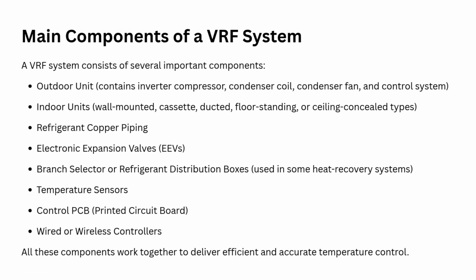Main components of a VRF system. A VRF system consists of several important components. The outdoor unit contains an inverter compressor, condenser coil, condenser fan, and control system. Indoor units include wall-mounted, cassette, ducted, floor-standing, or ceiling-concealed types. Refrigerant copper piping is used for refrigerant distribution. Electronic expansion valves, EEVs, control the refrigerant flow. Branch selector or refrigerant distribution boxes are used in some heat recovery systems. Temperature sensors monitor and control the system. The control PCB, printed circuit board, manages overall system functions. Wired or wireless controllers provide a user interface for operation. All these components work together to deliver efficient and accurate temperature control.